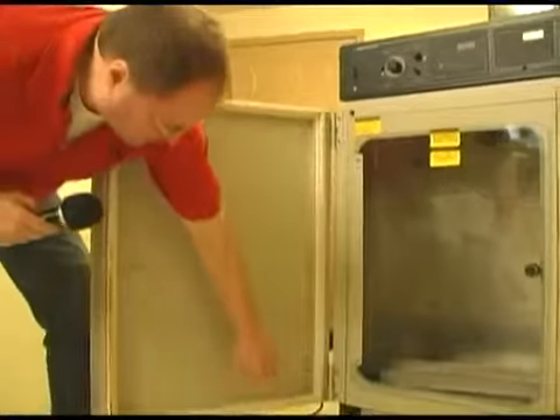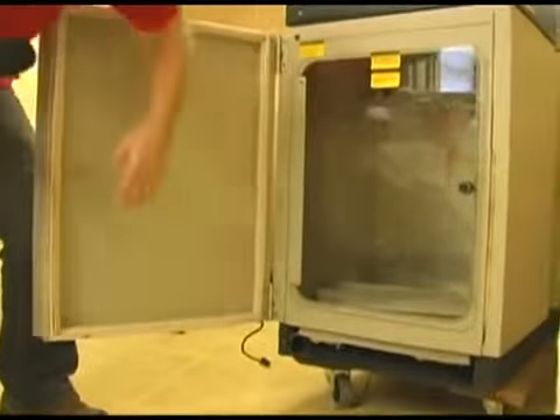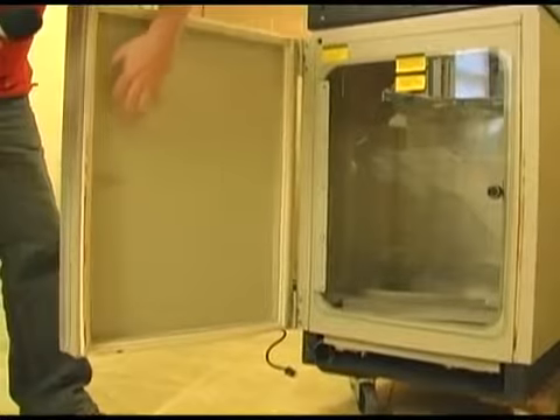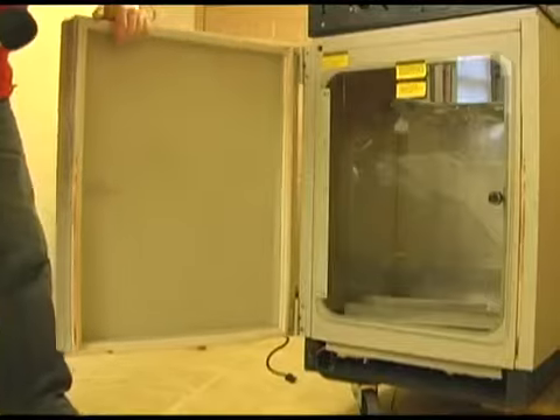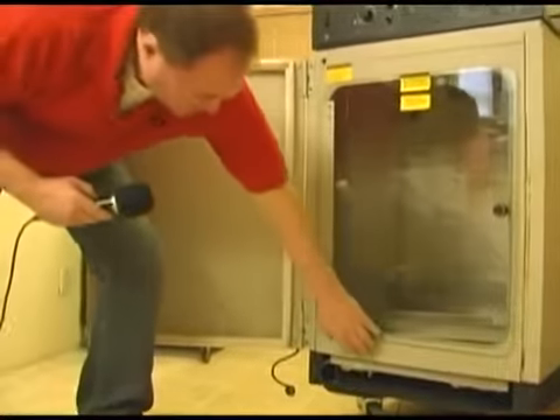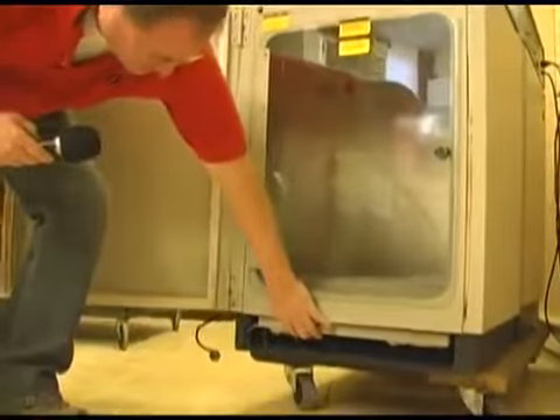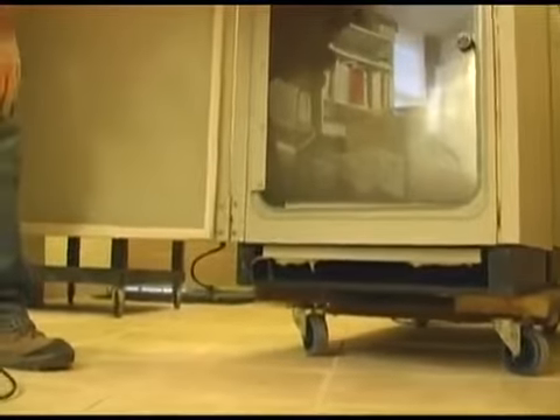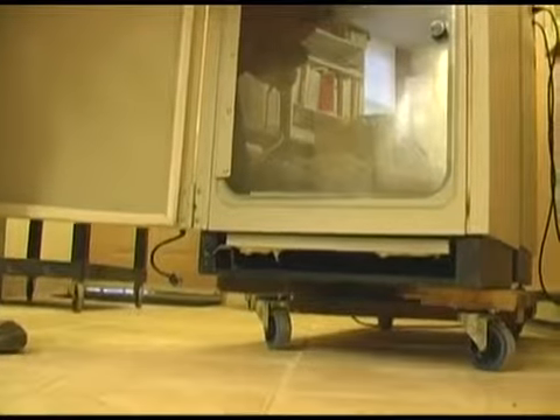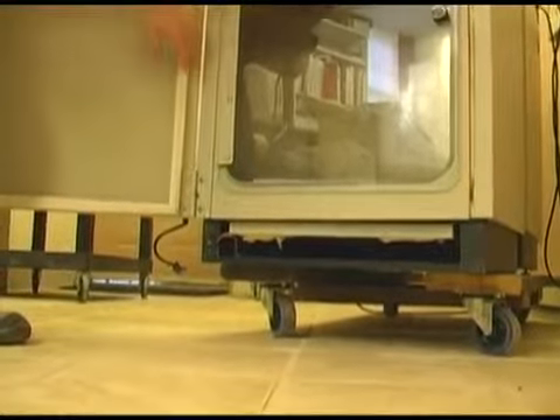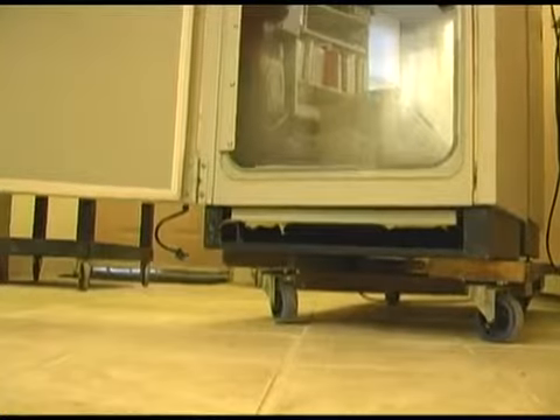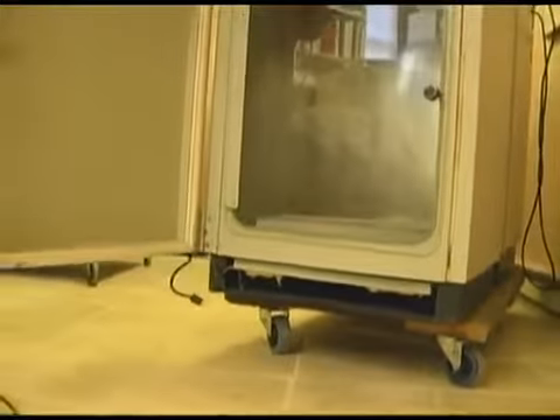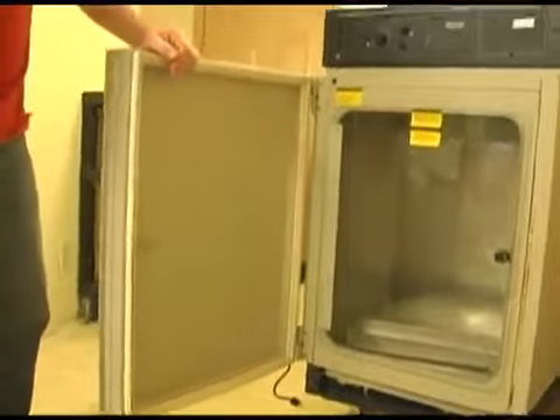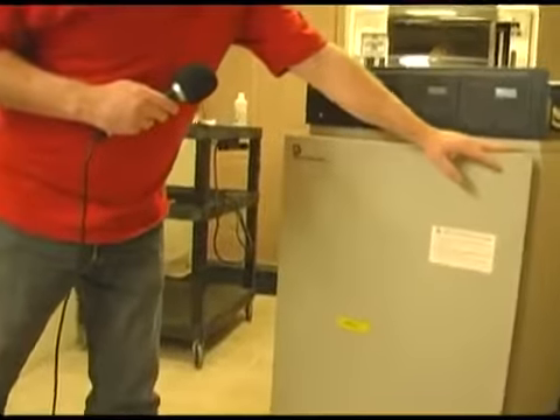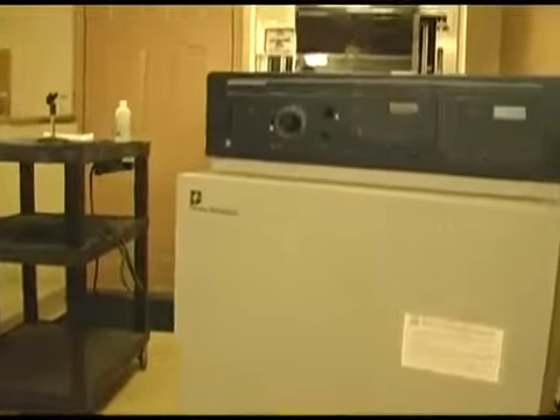The outer door on this particular unit, and most of them, is heated. That's what the power line down here is for. It takes 120 volts, and it's one long heater throughout the door. Underneath here, you're also going to see a heating pad. That heating pad is how this instrument controls humidity. It doesn't have much of a control for humidity. It's simply you put a pan of water in the bottom, and you'll get 90% most of the time. So it gives you limited control. Some incubators have actually controls so that you can put a set point for humidity.